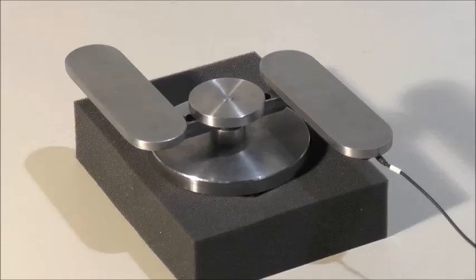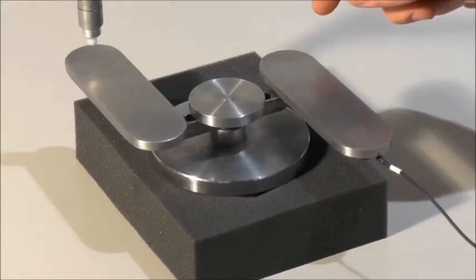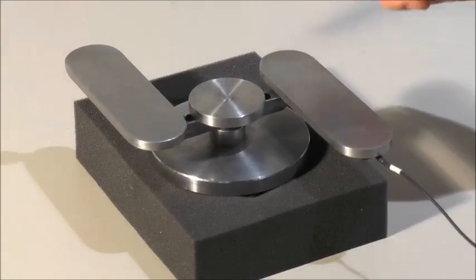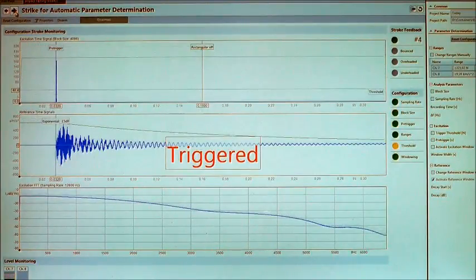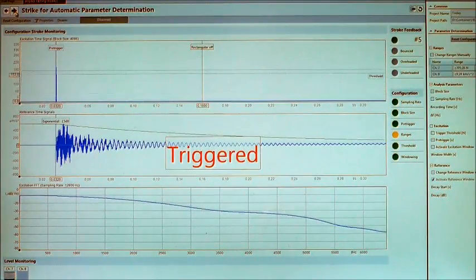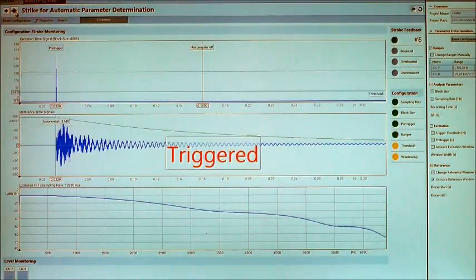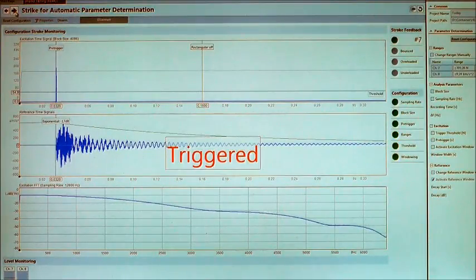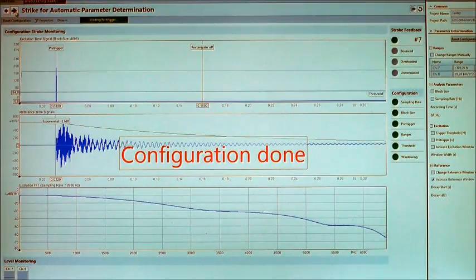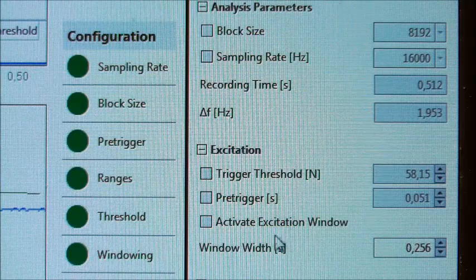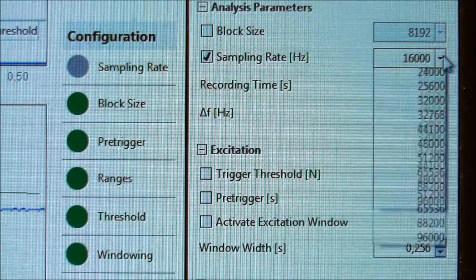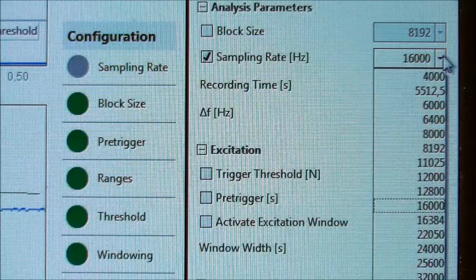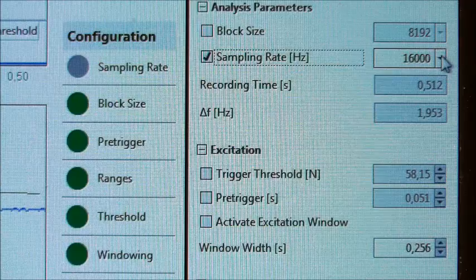Now you are asked to strike your test object. ArtemiS Suite automatically determines the optimal analysis settings for your test object by means of the single strikes. Sampling rate, block size, pre-trigger, ranges, threshold and the analysis windows are all adapted to your test object by an intelligent algorithm. We are already done. That was simple. It goes without saying that the analysis parameters can also be indicated specifically, just as you prefer. As for me, I would like to keep sticking to the parameters determined by ArtemiS Suite.